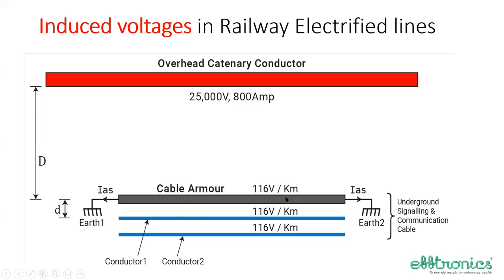For example, if you consider this as a cable, the cable has an armor, and I have shown here only two conductors. So all three are going to have 116 volts. But these 116 volts will have a 180 degrees phase difference with the top one. Induced voltage. Now, if the cable armor is earthed, this 116 volts per kilometer can create a current which flows into the earth. This current will be opposite to the 800 amperes.